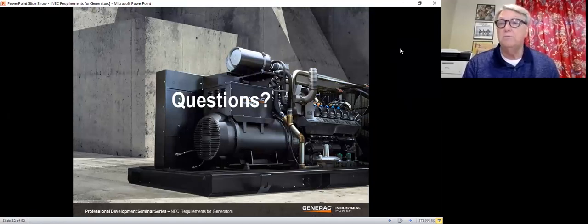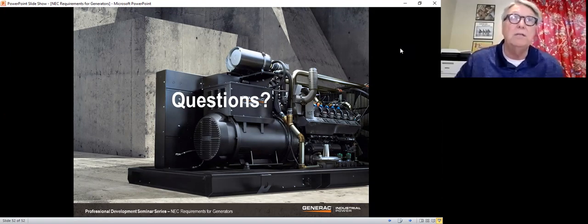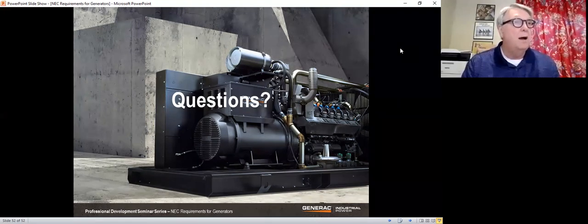First of all, read the spec. We find some engineers go out, they grab a boilerplate spec, they copy and paste, and in it goes. And they don't even read the spec. They just figure, oh, this is our generator spec. And you look through it, and it'll have some paragraphs in here that refer to natural gas and some that refer to diesel, and you don't know what to do. For instance, if it's an emergency generator, you have to specify that it's an emergency generator. You have to specify that it's got an NFPA 110 controller. You have to specify that it has a permanent magnet alternator. You've got to specify maybe that it has an LSI breaker. You've got to specify that it have a remote annunciator and an emergency stop and so on.